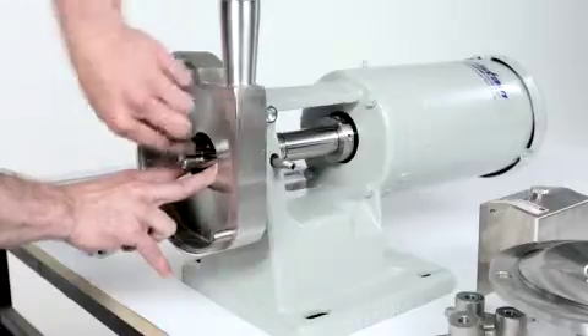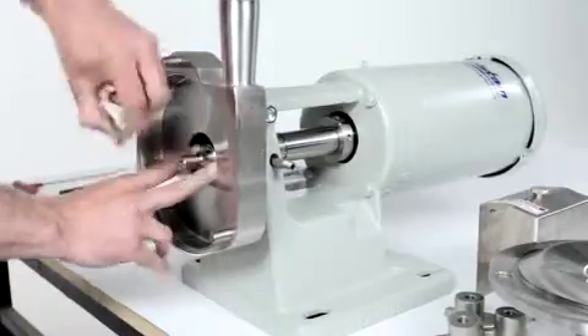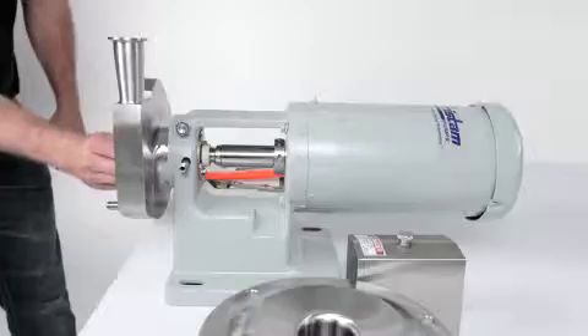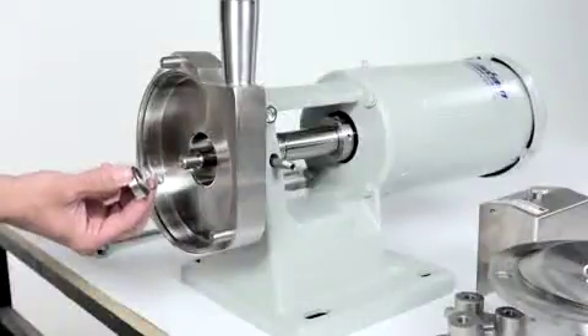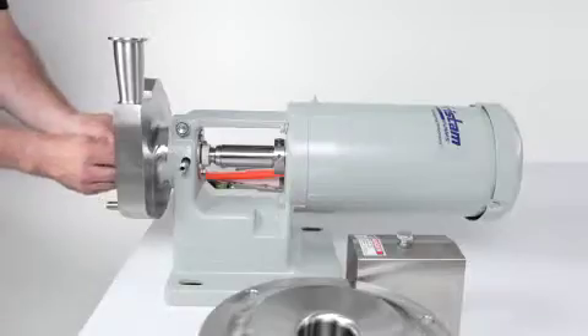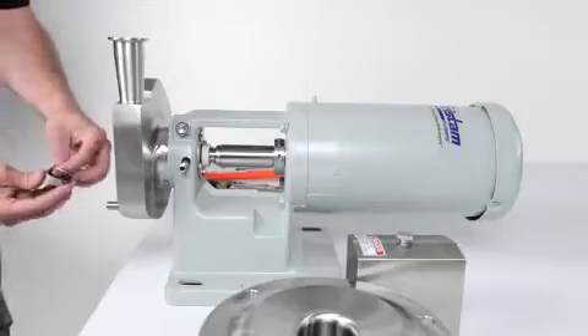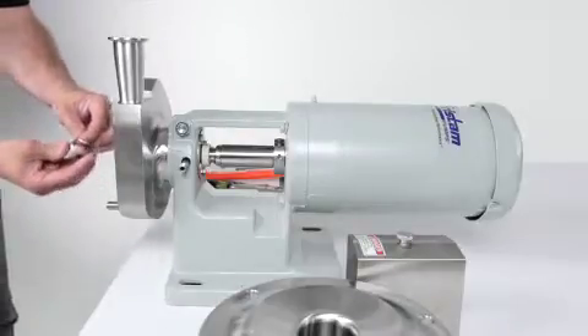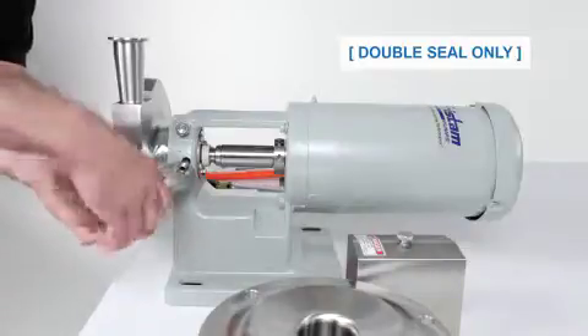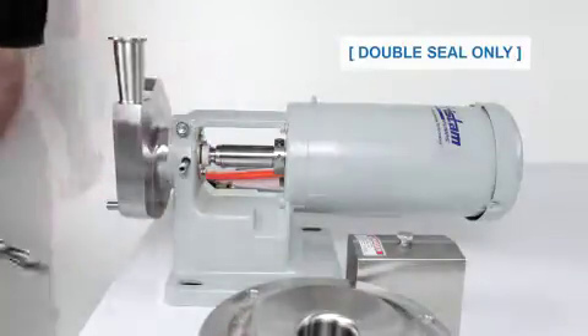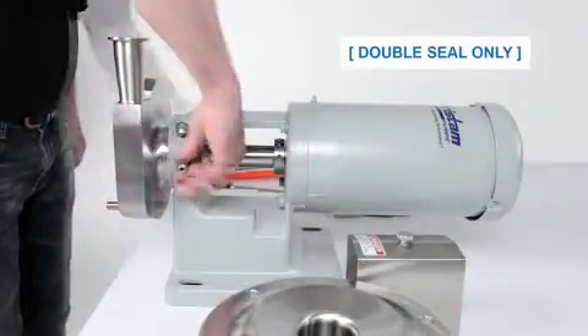Remove the impeller key by compressing the seal spring. Remove the front seal driver and seal spring and discard them. Remove the rotating seal, seal washer, and O-ring and discard them. For double seal pumps with a water flush, remove the water pipes.